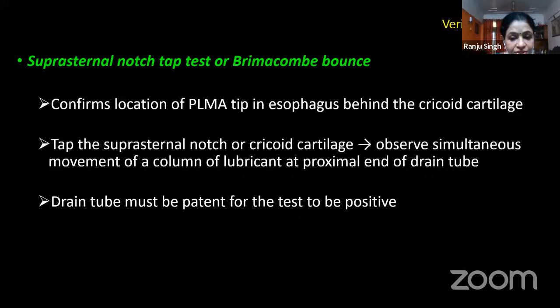Although this is classically defined and described for a ProSeal LMA, it can be done with cuffed second generation devices very well. After you've placed the device, you can tap on the suprasternal notch or the cricoid cartilage. While doing this, observe for the movement of a column of lubricant that has been placed at the proximal end of the drain tube. However, you must remember that the drain tube must be patent for this test to be positive.